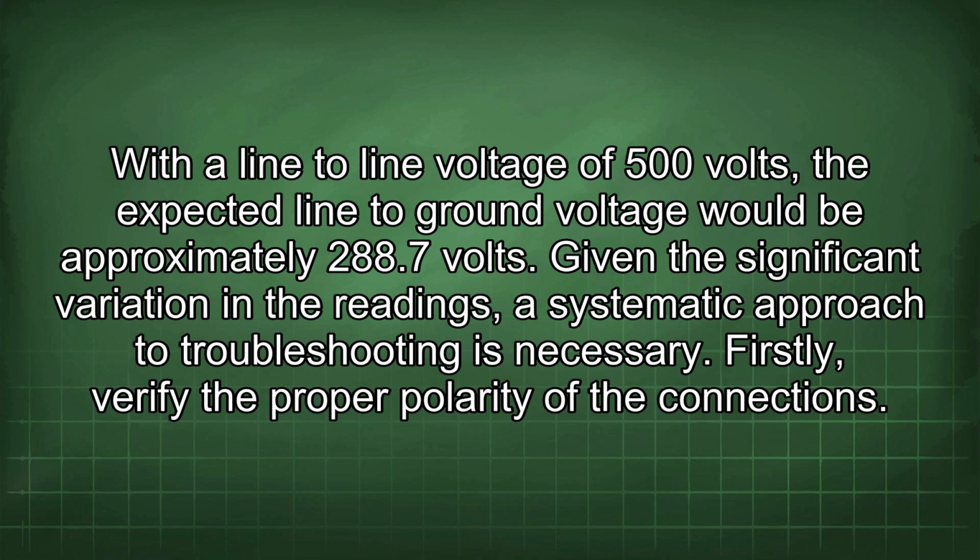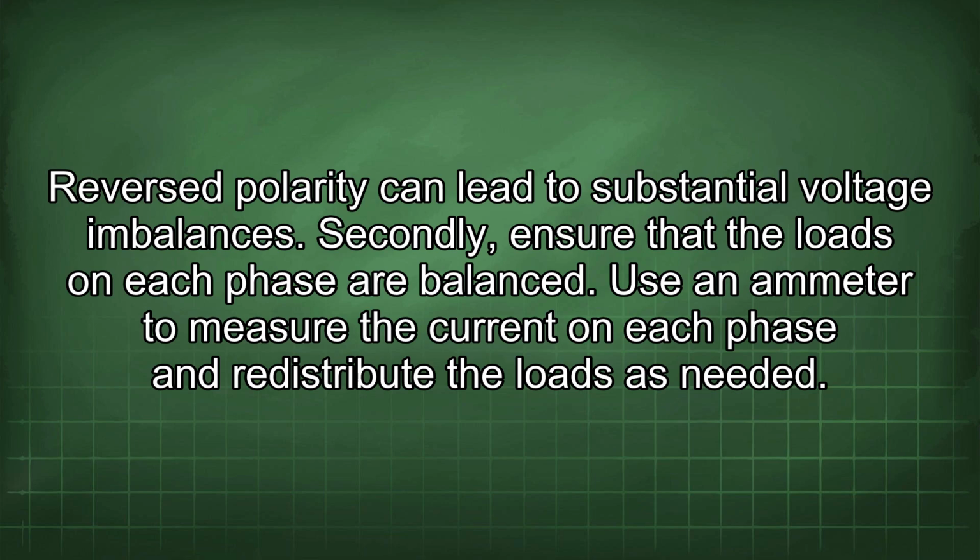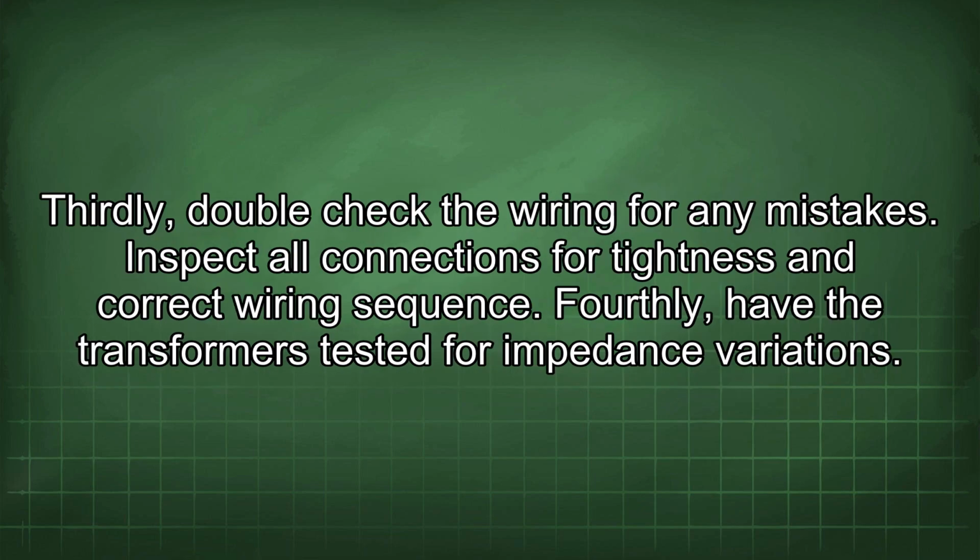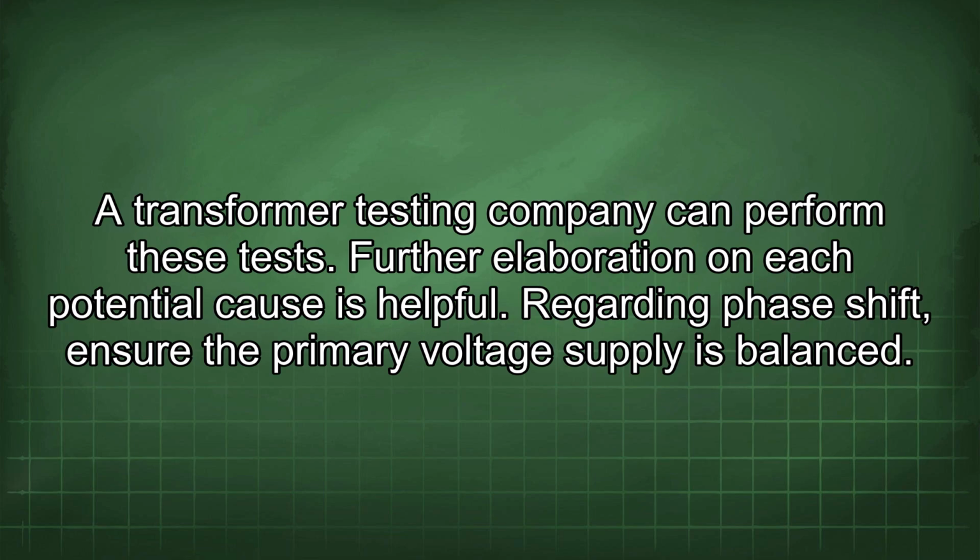Firstly, verify the proper polarity of the connections. Reverse polarity can lead to substantial voltage imbalances. Secondly, ensure that the loads on each phase are balanced. Use an ammeter to measure the current on each phase and redistribute the loads as needed. Thirdly, double-check the wiring for any mistakes. Inspect all connections for tightness and correct wiring sequence. Fourthly, have the transformers tested for impedance variations. A transformer testing company can perform these tests.